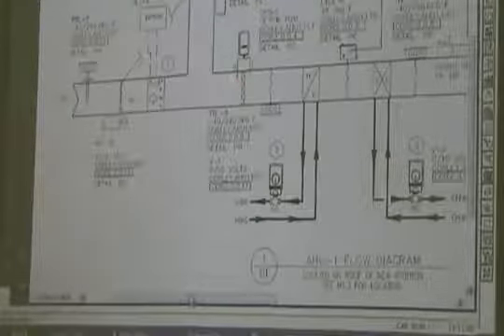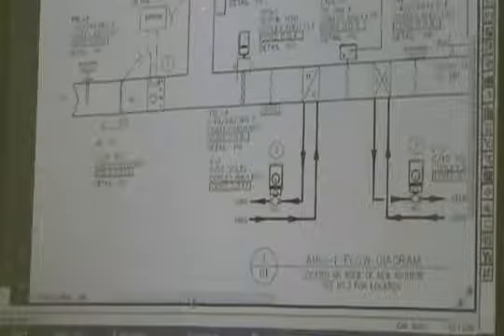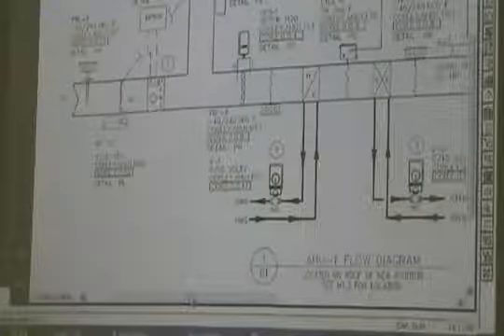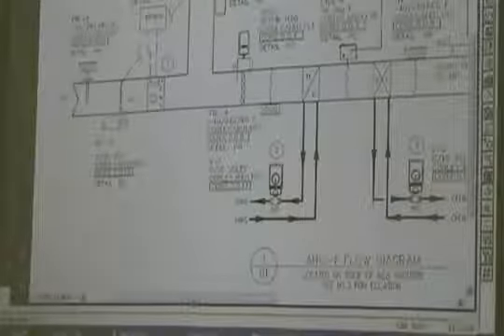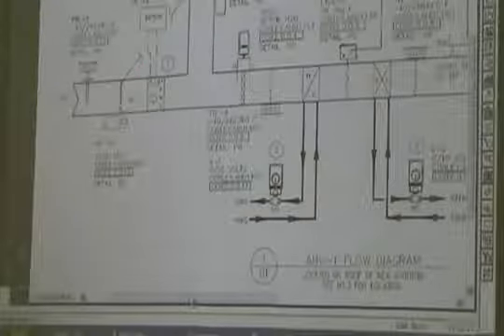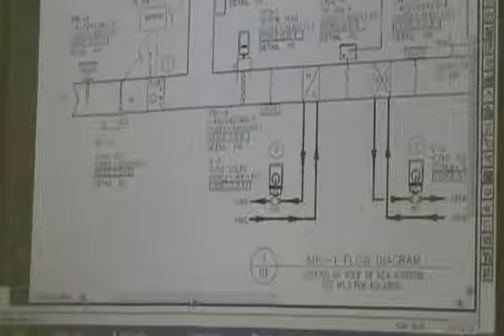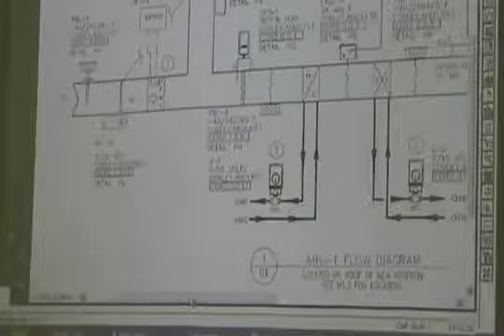Filter, differential pressure switch across the filter. Now, here's our added thing that we didn't have in the other air handler. This is showing a return air damper and outdoor air damper. Both of them have a motor on them, but they're both showing the same point on here. So that's just telling you the same signal's going to both actuators. But it's also showing this line right here that's dashed in the middle, showing that they're mechanically linked. Okay? So one physically cannot open without the other one closing.